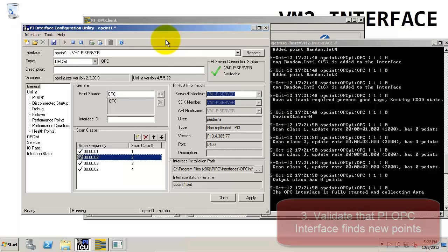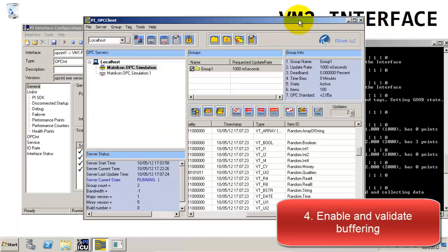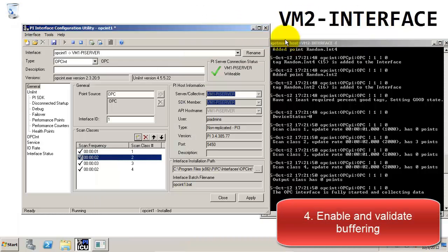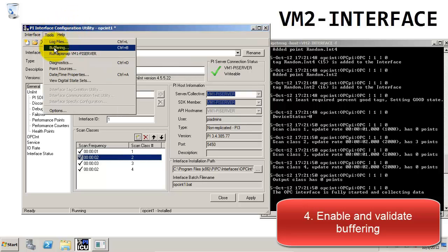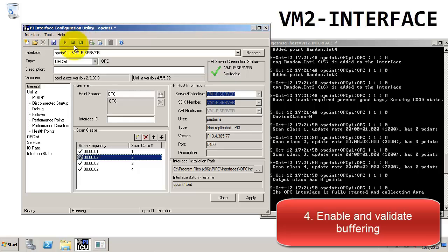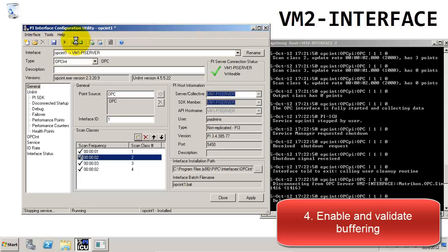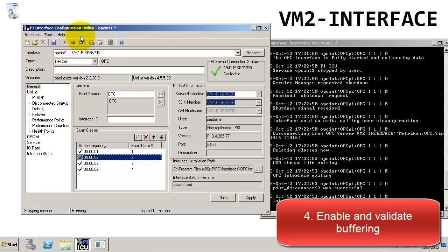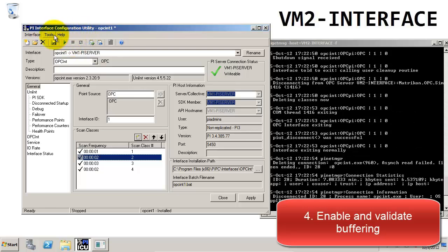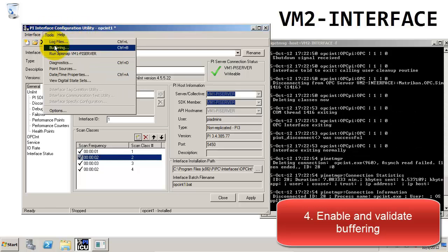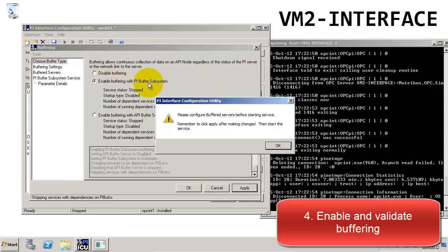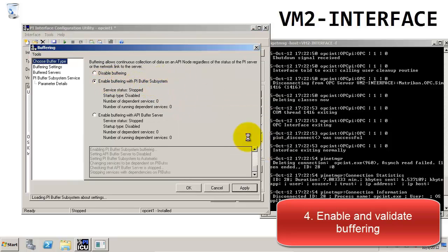Now that we have working OPC tags, the next thing we would like to do is to enable buffering. To enable buffering, we go to Tools and Buffering. But before we do that, we need to make sure that the interface is stopped. Once we've stopped the interface, we go back to the Buffering settings under Tools and Buffering, and we will choose to enable buffering with the PI Buffer subsystem.